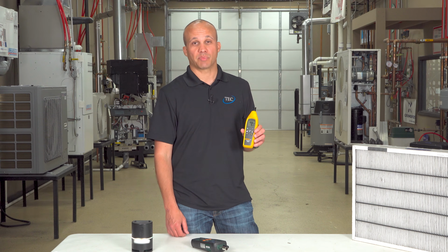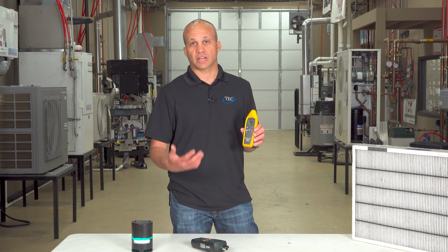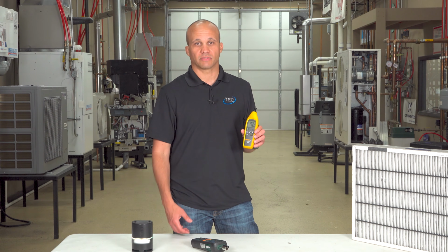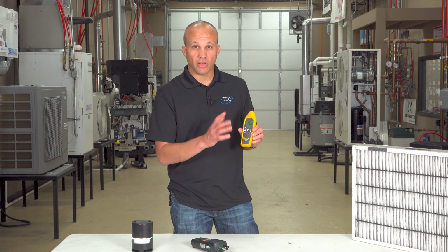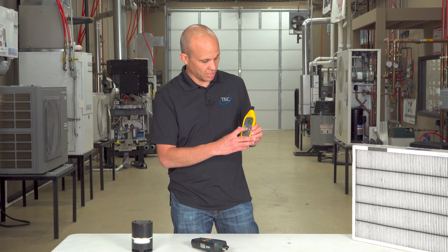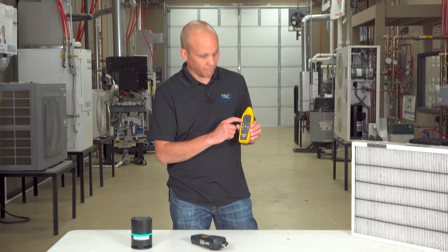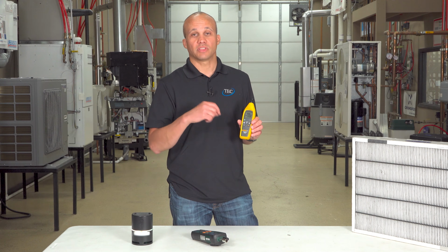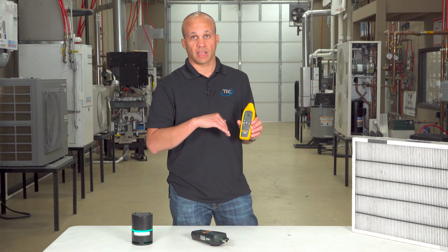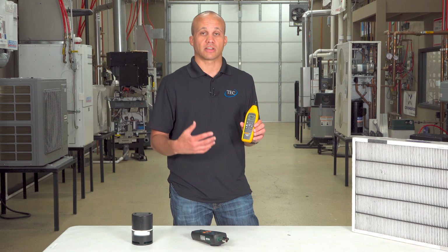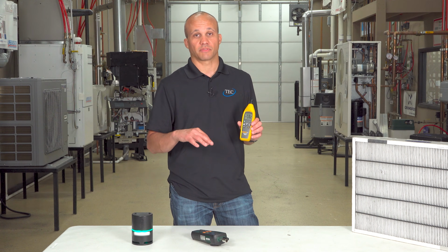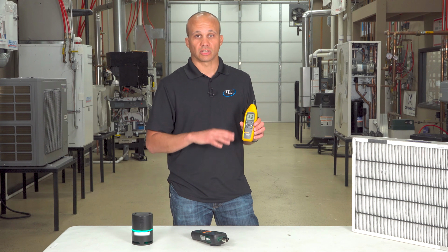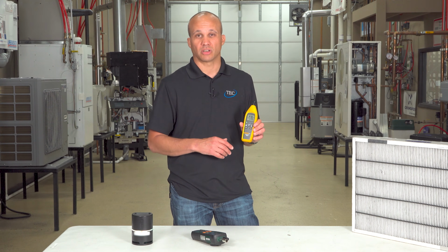It's really common for that to happen in buildings because of numerous reasons: oversized equipment, leaky building envelopes, all kinds of things. But right now, let's just try to measure it in your space. So I've got temperature and relative humidity there. The other thing to think about on some of these tools is if I toggle between here, I can scroll down and I can read dew point, 55 degrees. Dew point means if this space temperature gets below the dew point of the air, it will condense, just like dew condenses on your grass or your car windshield. And if it condenses, it's much more likely that bad stuff is going to be growing in behind the walls and stuff like that. So the dew point always needs to be fairly low. Right now we're at 55, 54. That's really good. No problem there.